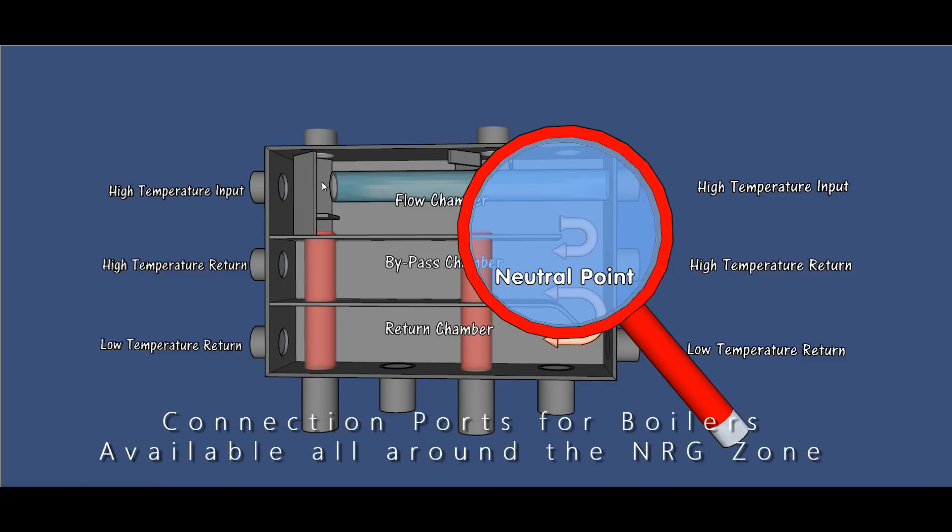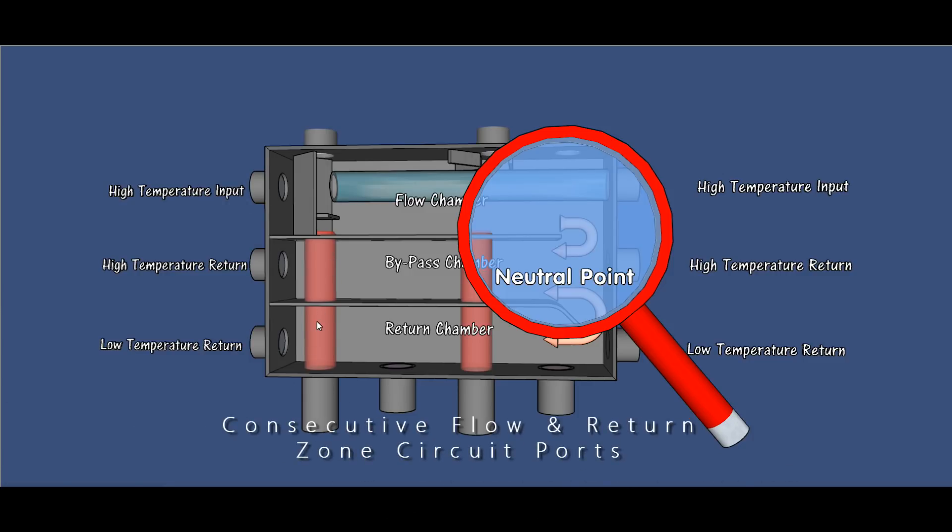If you're pumping to a boiler from the Energy Zone manifold, you pump on the return connection to the boiler. Remember, the flow to a boiler is the return pipe also. If you're pumping to a zone, for example, you'd pump on the flow out.